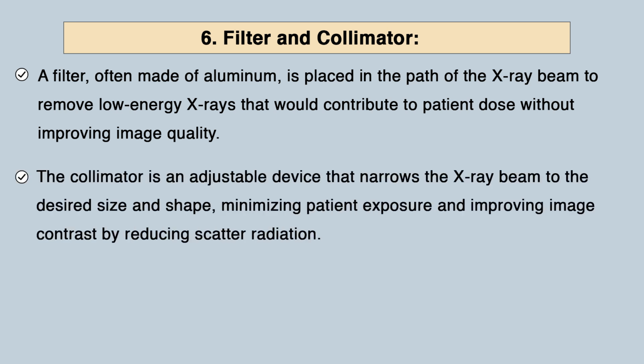The collimator is an adjustable device that narrows the X-ray beam to the desired size and shape, determining the patient exposure and preventing image distortion. Each of these components plays a crucial role in ensuring the X-ray tube functions efficiently, producing high quality images while minimizing patient dose.